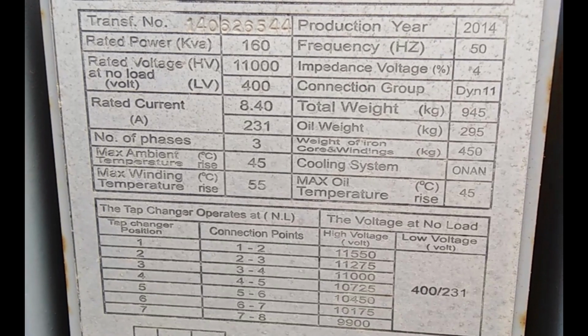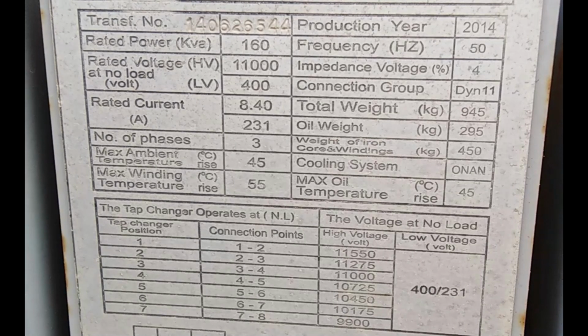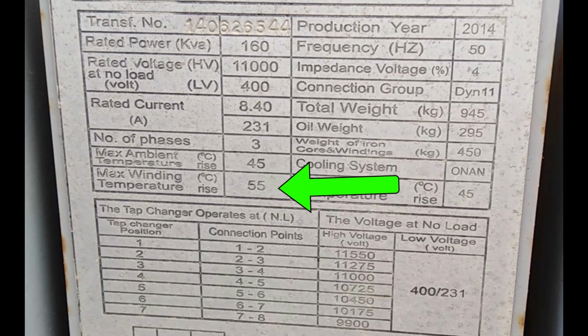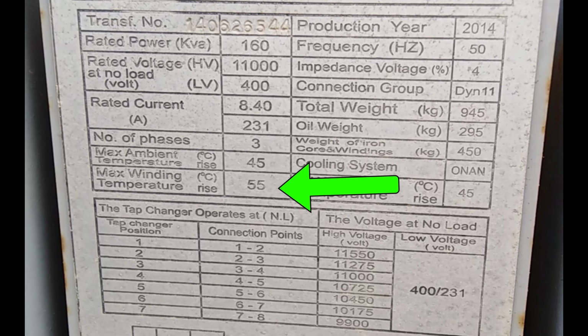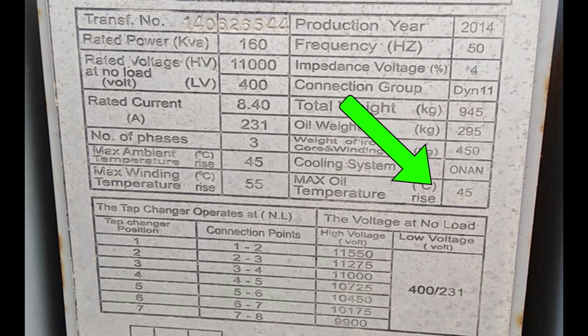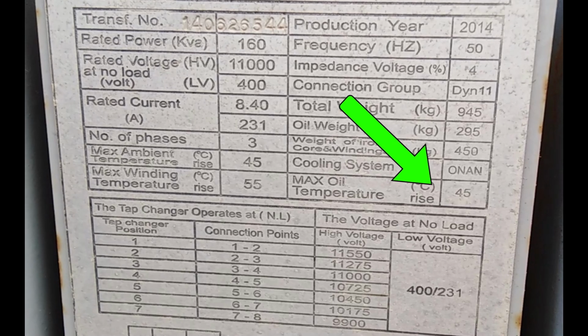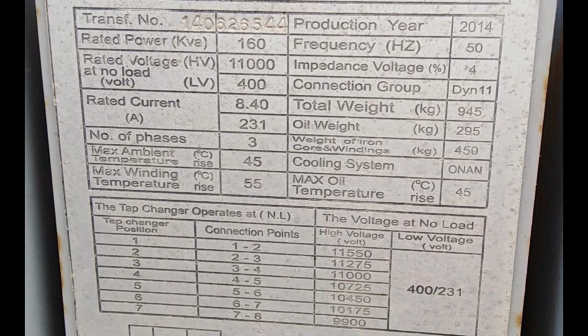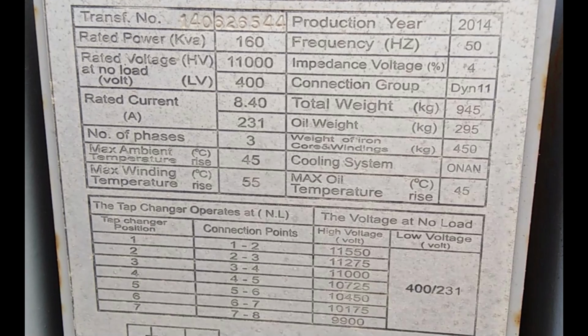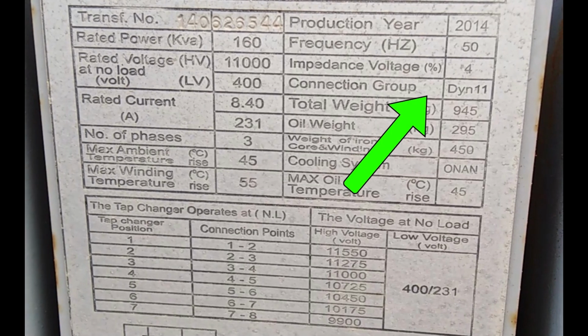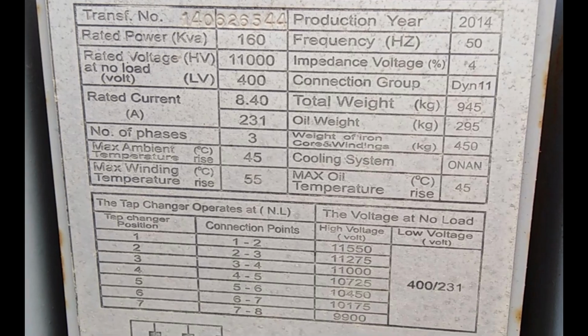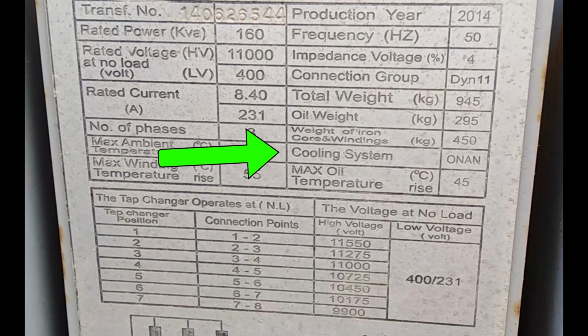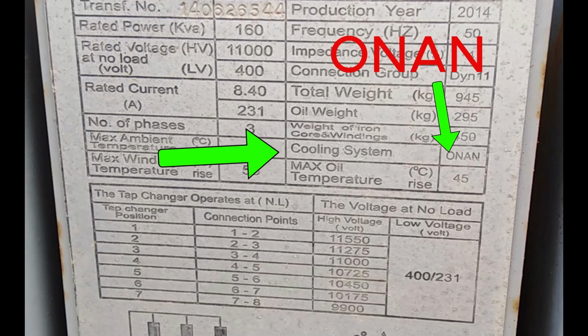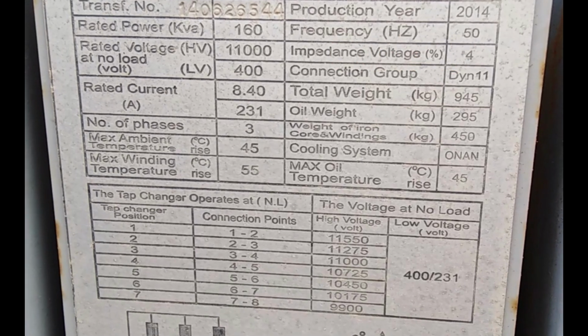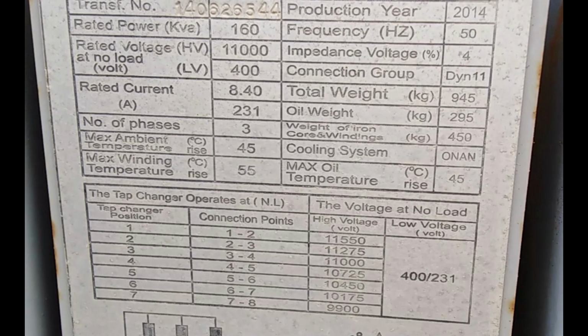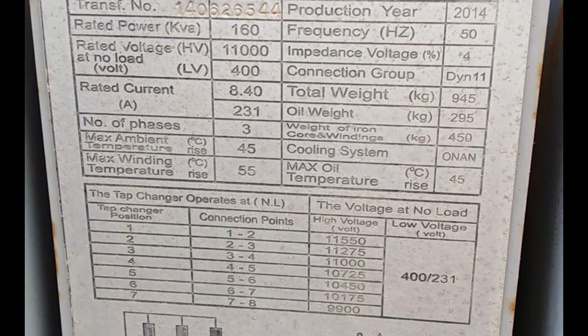Temperature limits are also crucial. With maximum ambient temperature at 45 degrees Celsius, maximum winding temperature at 55 degrees Celsius, and maximum oil temperature at 45 degrees Celsius, these limits ensure the transformer operates safely without overheating. The connection group, noted as Dyn11, tells us about the transformer's winding connections and phase shift, important for system compatibility and ensuring the power flows correctly. Cooling method, ONAN, or oil natural air natural, means our transformer self-cools by circulating oil and using the natural airflow. No extra energy is needed for cooling, making it efficient and reliable.